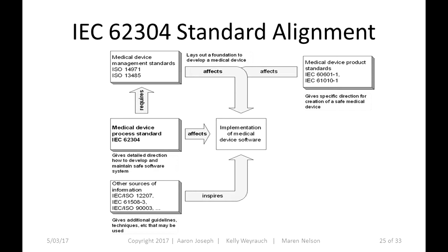The 62304 software standard doesn't stand alone. It works in harmonization with the 13485 standard to define the specifics around software development for medical devices. So the 62304 works well with both the 13485 and with the 14971, the risk management procedure.